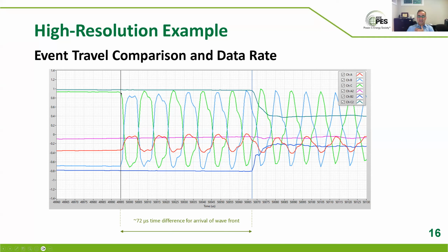Every 8 microseconds, a wave arrives at this terminal, the first one being the first wave that arrives. We don't necessarily know when it left its fault location, but then we see another reversing wave arrived about 8 microseconds later. The nice thing here is that you can go ahead and count and say, oh, 10 of these happen in 82 microseconds. So every one of these reflections is not actually 8, it's 8.2. You get even finer resolution than your microsecond sampling.